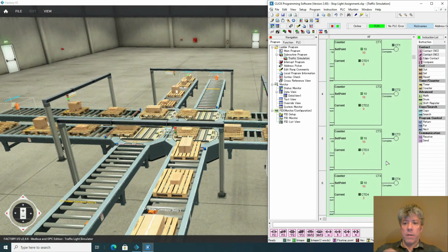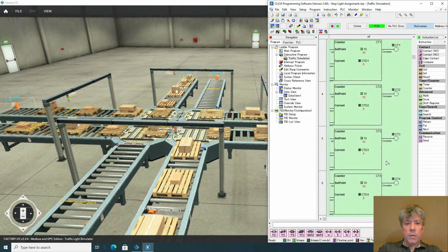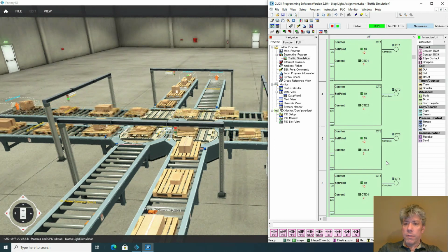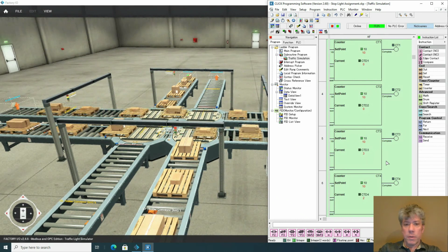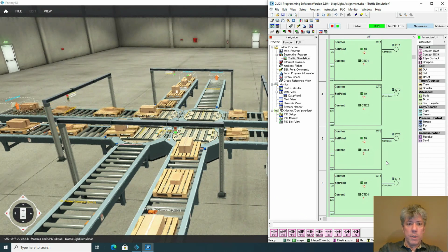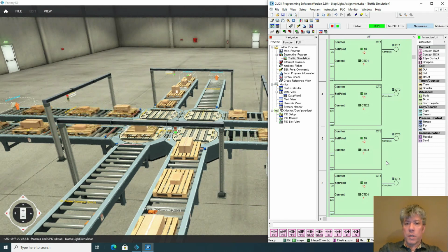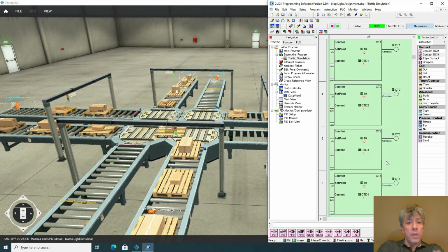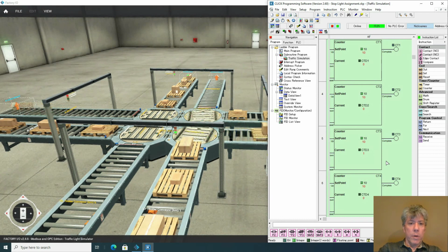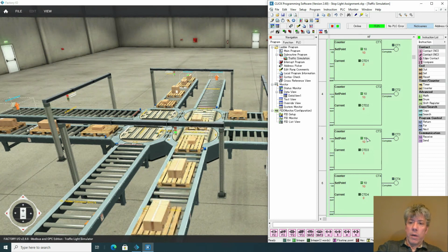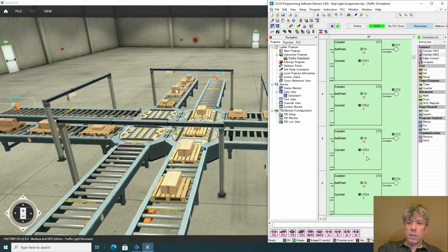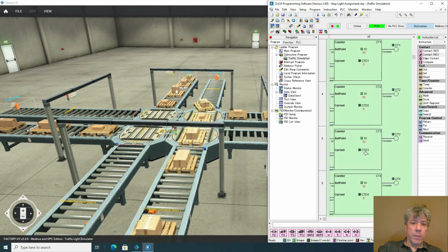Let's see if the count for direction 3, which is going from right to left across our view, ever goes down to 0 when the last pallet comes through. Let's see, there's one drop, here's another drop. So as far as it's concerned, there's still a pallet in the intersection. And what that will do is prevent the turntables from turning properly for direction 2. Yeah, there it is. Now obviously we could go in here and correct it. We can override this value, but there's not really much of a point.